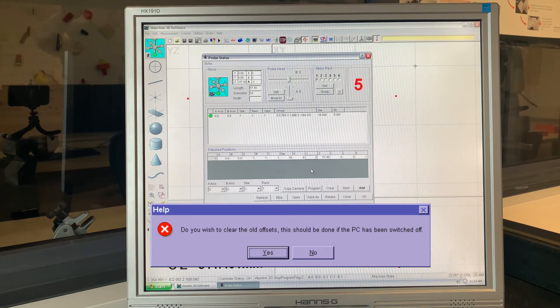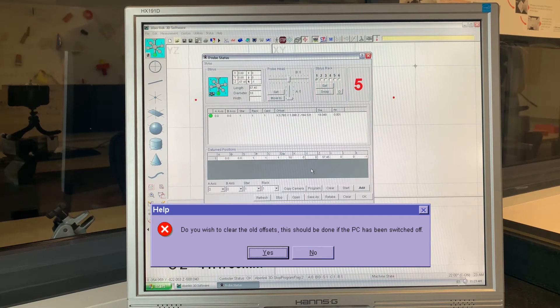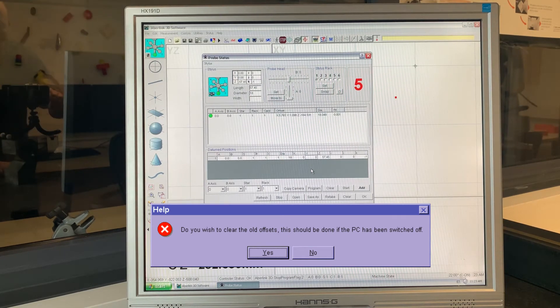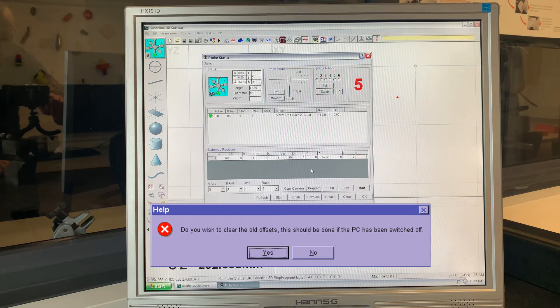When you have completed the fifth point in this position, the following point will appear. If the offset previously measured relates to the previous stylus, click on yes. If the offset previously measured relates to the current stylus and you wish to keep them, click on no.